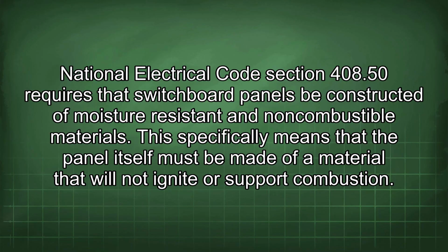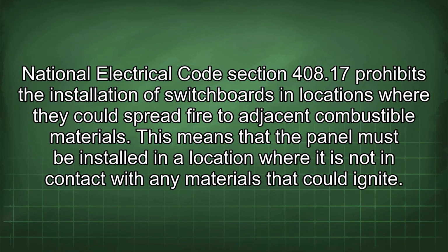National Electrical Code Section 408.50 requires that switchboard panels be constructed of moisture-resistant and non-combustible materials. This specifically means that the panel itself must be made of a material that will not ignite or support combustion. National Electrical Code Section 408.17 prohibits the installation of switchboards in locations where they could spread fire to adjacent combustible materials.